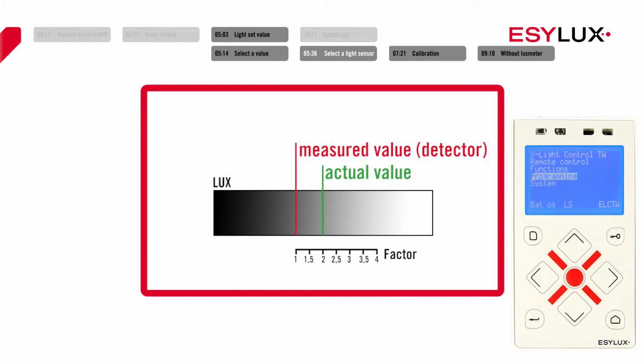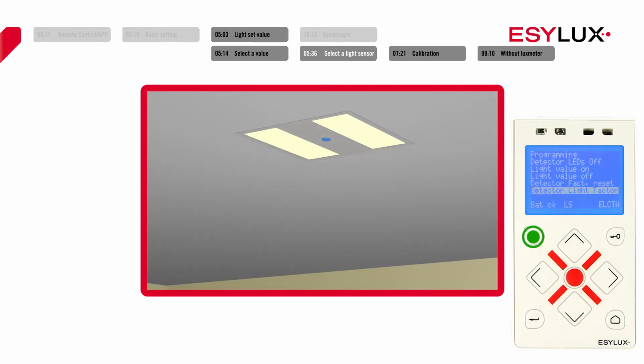If the light control deviates from the target light value, you can change the light value factor of the presence detector. The light value factor is set to a value of 2.5 in the factory. If the area is too dark, the light value factor can be reduced. If you use a system with multiple presence detectors, then the detector's light sensors may influence each other. To deactivate the light sensors of an individual presence detector, point the remote control towards the relevant detector and deactivate the detector's light value measurement.